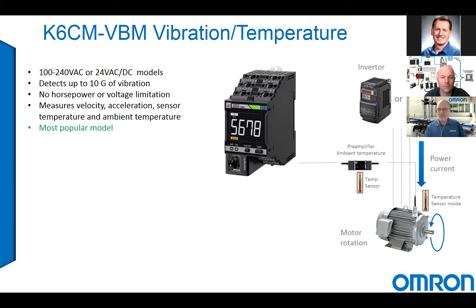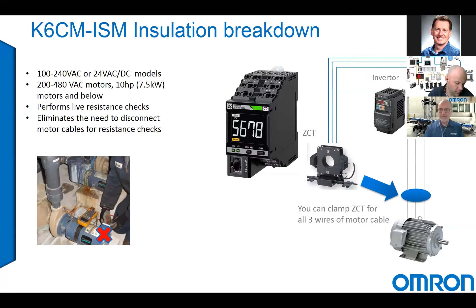And the last one is the insulation breakdown. Normally, to verify the insulation breakdown, you need to open the junction box, unwire the motor from the supply, and then use your Megger or your ohm checker. By doing so, Omron allows you to connect directly on the motor with a 3-phase current clamp and do the math inside the relay to verify if there's leakage down to the ground of your motor. And again, that is done in real time, obviously.